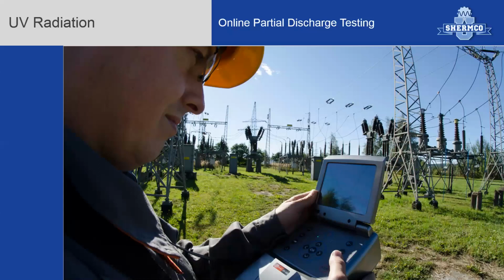So typically when you're using this type of camera, we see the gentleman in the photograph, he has the lens of the camera pointing up into the substation. He's looking through the viewfinder. What he will be seeing is little flashes of white light, the UV light. Now, if he's pointing that camera into, let's say, just the sky, but not a focused target, he may be getting many little random bursts of light. These are little sun flares that he's picking up, little ultraviolet radiation.